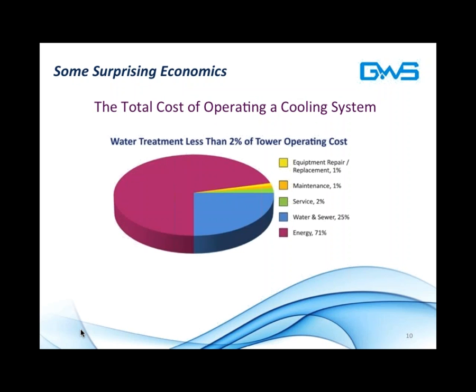What are the economics of water consumption in buildings? Many of you have heard this if you've been a rep of ours. If you're a customer, this might surprise you. The total cost of operating a cooling system, if you factor in the purchase of a cooling tower, the chemical costs that are used to treat that water on an ongoing monthly basis for the life of the equipment, the water costs and the energy costs are all inputs that are over time very expensive. Many people look at the bills and they think, well, this cost is largely attributed to certainly the chemicals. The reality is much different.